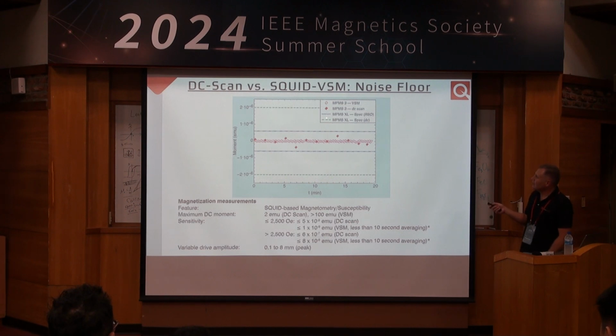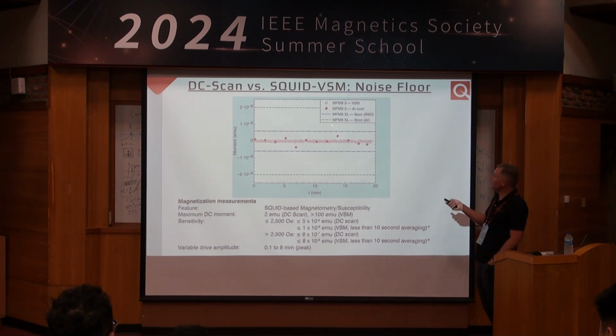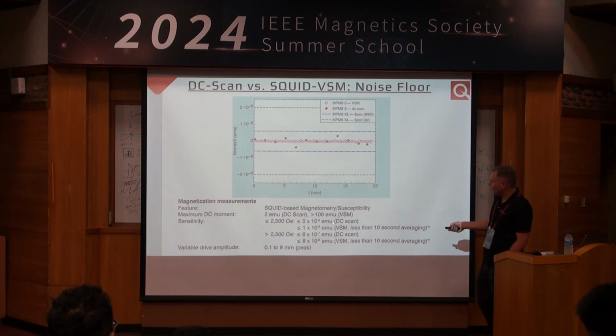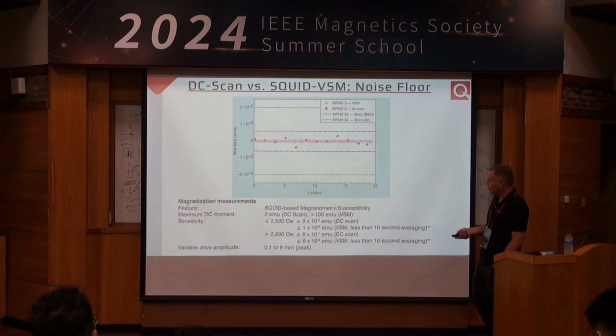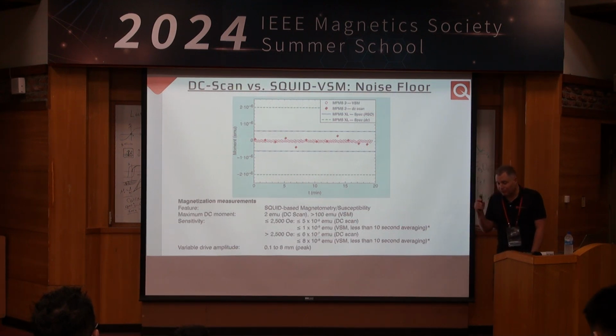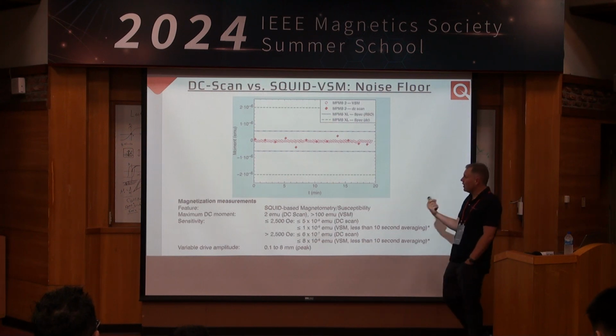All right, so in terms of sensitivity, the historical view of our system, the old system showed sensitivity on the order of micro EMU. So we've come a long way because now we're dealing with, again, 10 to the minus 8 sort of EMU sensitivities here. And the SQUID VSM mode always beats out the old DC scan mode and has a much larger dynamic range. We can measure all the way up to greater than 100 EMU. It's actually hard to put enough sample in the system to get a moment that large. It's a very powerful technique.